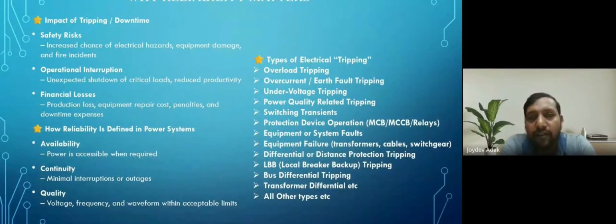High current for any drive, motor, etc. The primary initial current, the starting current, is much more than the normal full load current. Another is tripping in the protection device operation, that is the MCCB, relays, and mainly the circuit breaker. When a protection device operates through a relay, after the relay operates it sends a command to the circuit breaker or MCB or MCCB, wherever applicable.